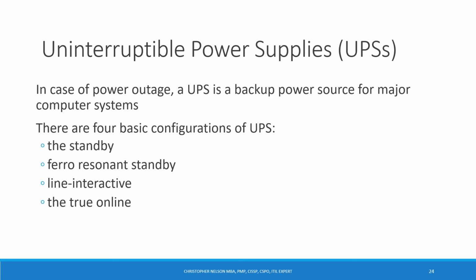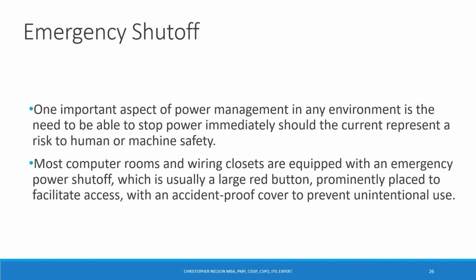UPS, uninterruptible power supplies. In case of power outage, a UPS is a backup power source for major computer systems. There are 4 types: the standby, ferro-resonant, line interactive, and the true online. For emergency shutoffs, we should always consider that one important aspect of power management in any environment is the need to be able to stop power immediately, should the current represent a risk to human or machine safety.